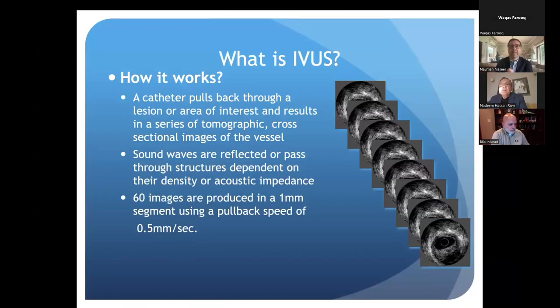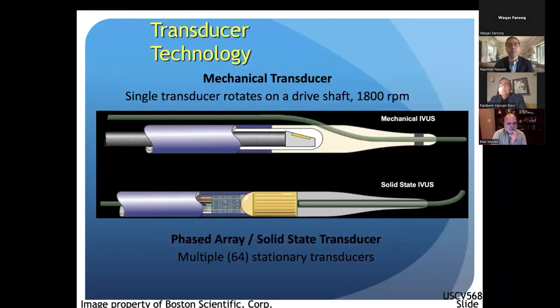A catheter pulls back through a lesion or area of interest and results in a series of tomographic cross-sectional images of the vessel. Sound waves are reflected or pass through structures depending on their density or acoustic impedance, and 60 images are produced in a 1 millimeter segment using a pullback speed of 0.5 millimeters per second. And what are the technologies available? We have two, Boston Scientific and Volcano, which is now taken over by Philips.